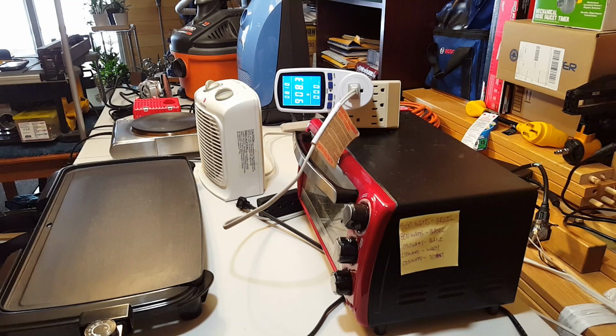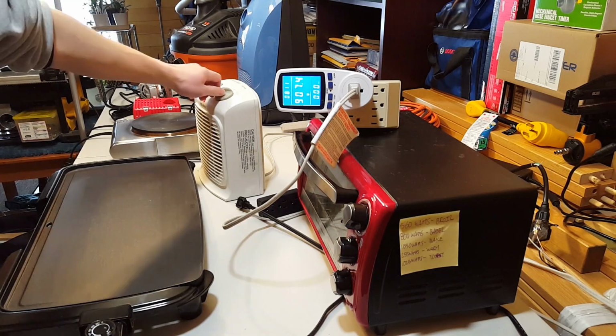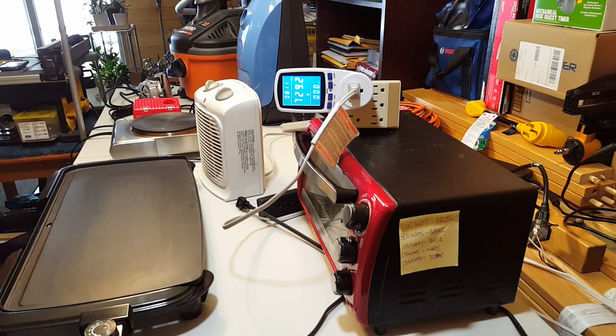I should also check the battery voltage as well so we can calculate the inverter inefficiencies. Battery voltage, this load, we are doing 52.2 volts. The low setting, 586 watts. Call it 590 watts for the space heater. AC amps, 5.0. Discharge from battery is 12.5. So that's going to be pretty much all the space heater type loads.